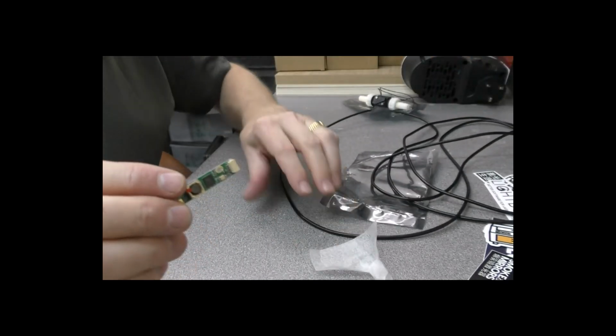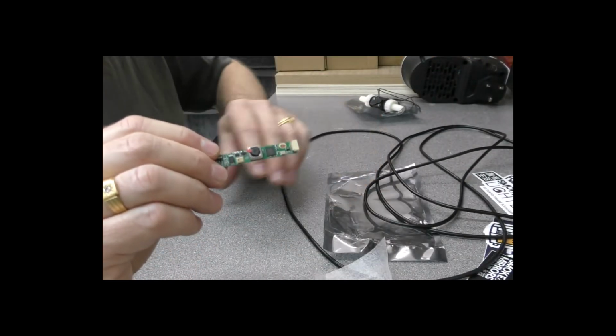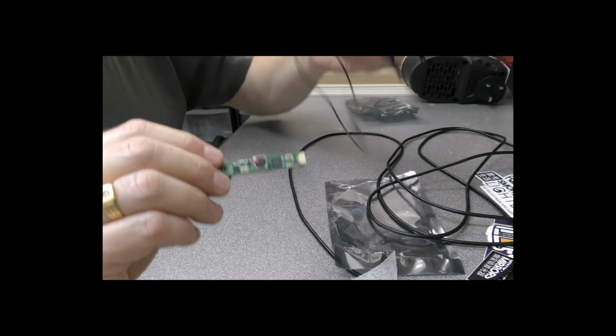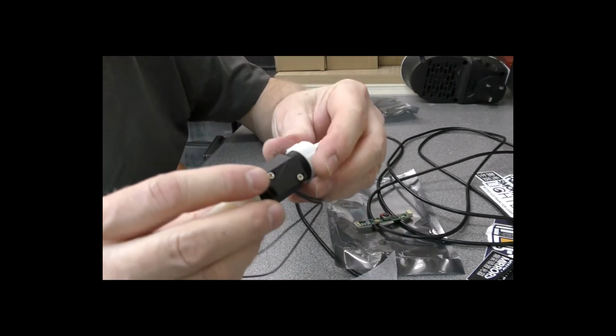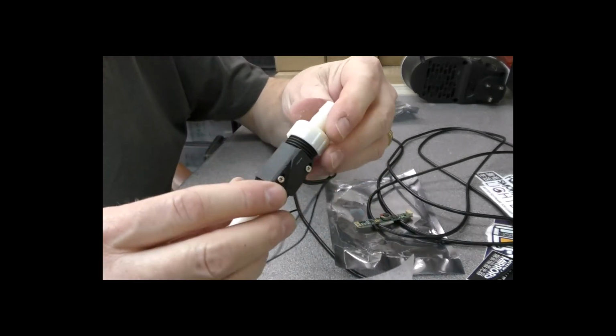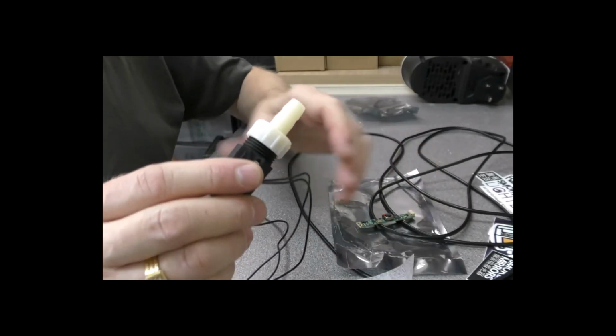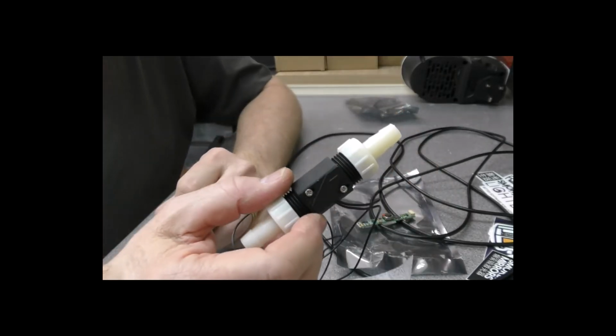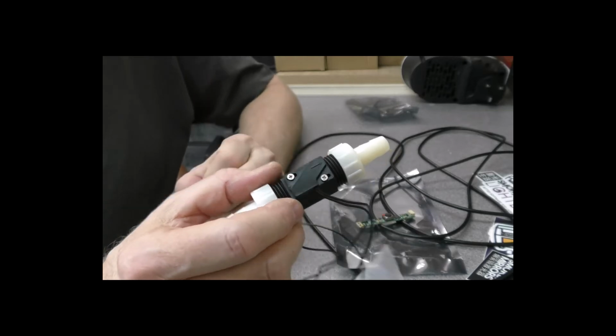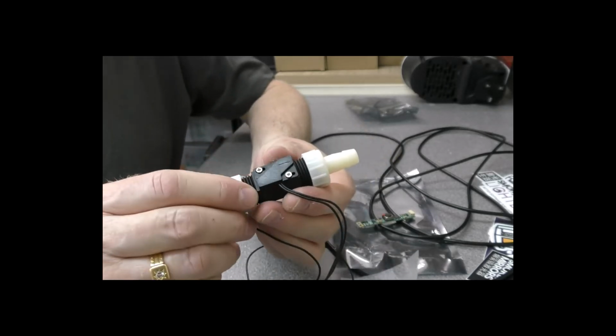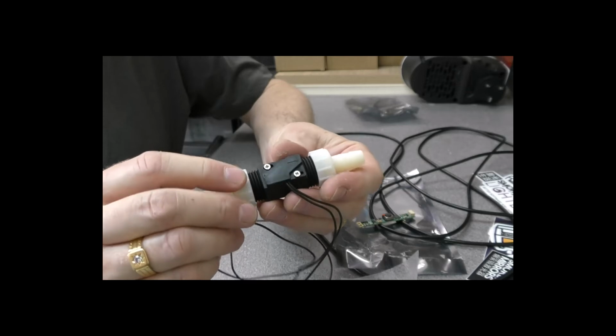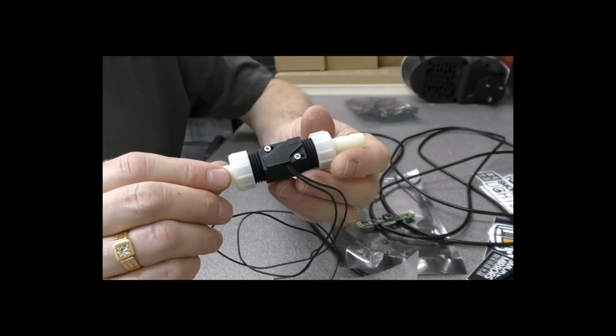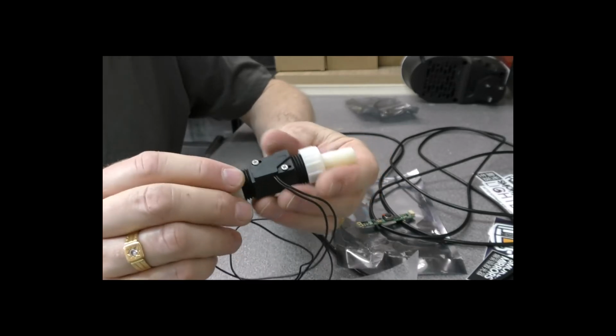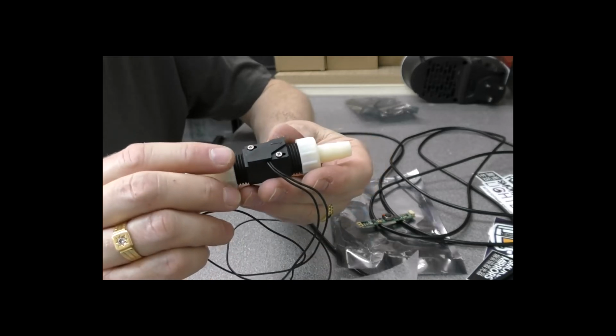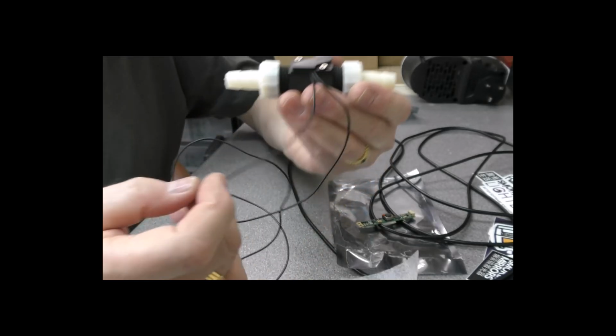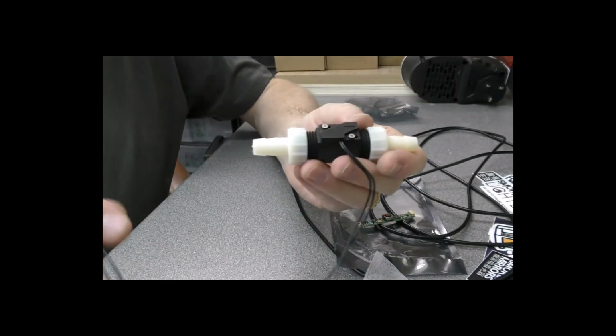So today's task really will be to get this flow switch put in and make sure it is working correctly. Strangely, the machine does not give you a warning - it just refuses to fire the laser when this flow switch isn't working. You would have thought some sort of warning would pop up saying the flow switch is not working.